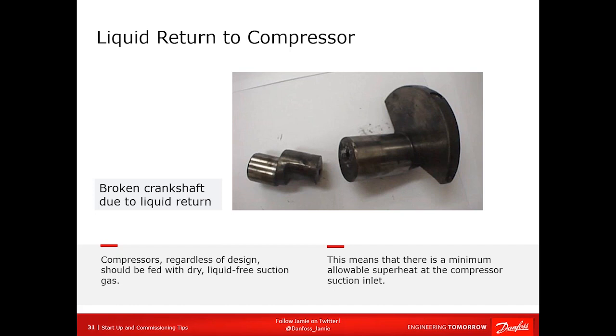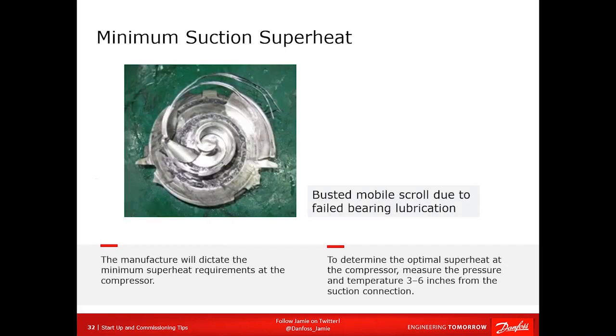even if the refrigerant didn't change temperature along the way. So on high temp systems like air conditioning and stuff like that, you're going to look for a pretty high suction temperature, or pretty high suction superheat. Why? You want to avoid this. So this is the opposite of a burnout. This is a drown out, if you want to call it that. Notice how clean this is, other than the fact that it looks like it blew up.